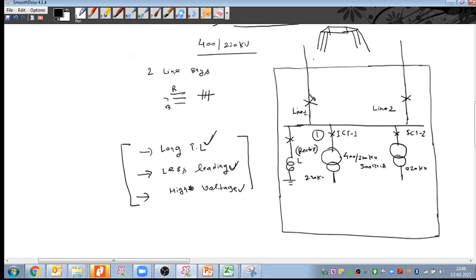So what is the problem if my voltage is increased? All the equipment is designed for 400 kilovoltage, right? So if the voltage is coming around 600 kilovoltage, or 500 kilovoltage, what will be the problem? This higher voltage will produce higher electrical stress on the equipment, and due to that higher electrical stress, the equipment insulation may flash over, may puncture. So to avoid this kind of electrical flashover and insulation failure, we have to limit this voltage under the rated voltage.